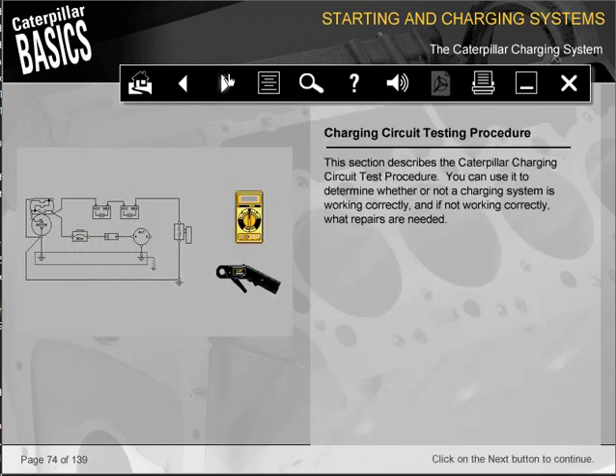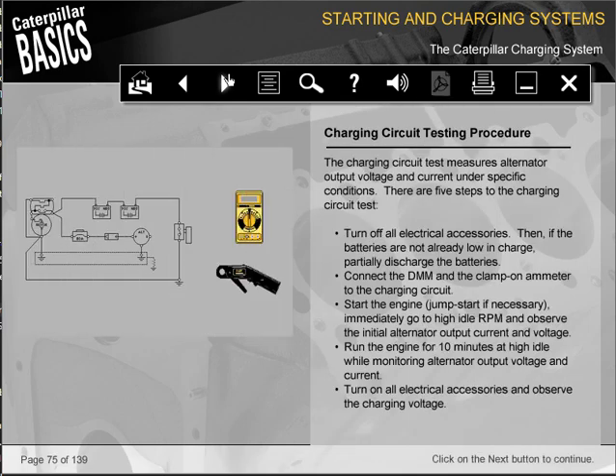This section describes the Caterpillar charging circuit test procedure. You can use it to determine whether or not a charging system is working correctly, and if not working correctly, what repairs are needed. The charging circuit test measures alternator output voltage and current under specific conditions. There are 5 steps to the charging circuit test.